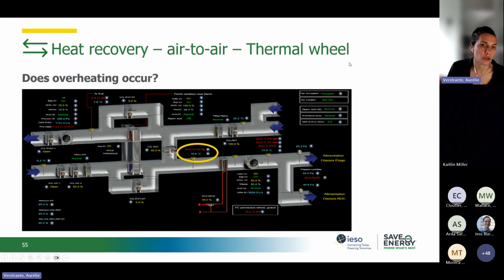Another question to address for air-to-air heat recovery: does overheating occur? Here in that example, it's a good example with a good control strategy, but sometimes when heat recovery systems are not optimized, you can recover more heat than needed, and it creates overheating in the rooms supplied.